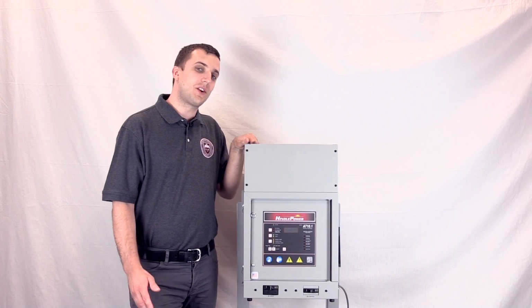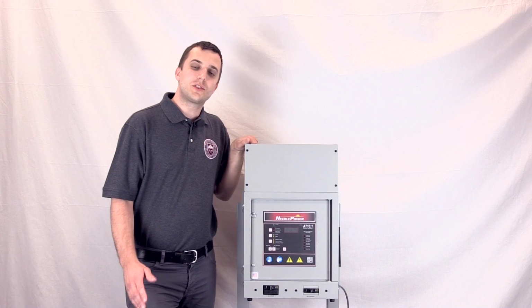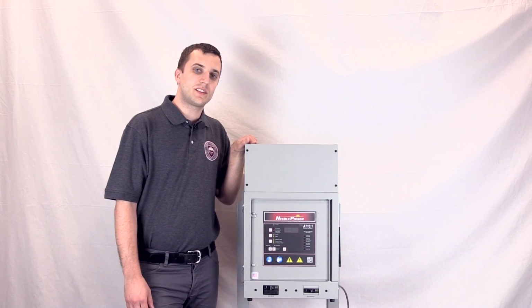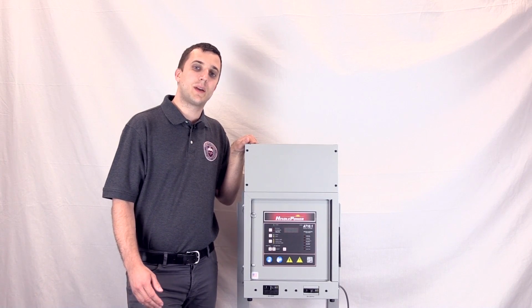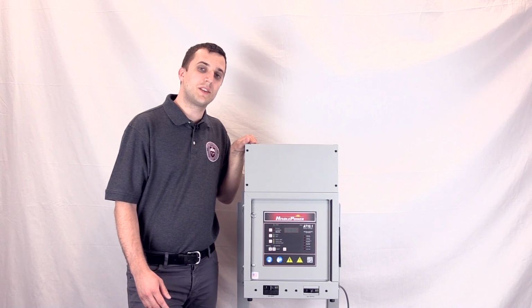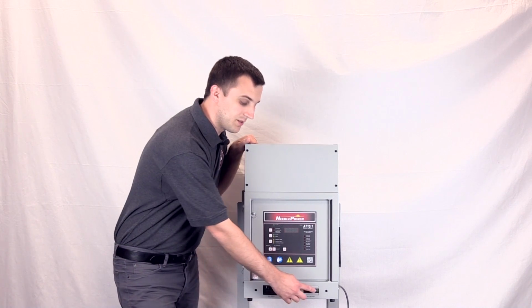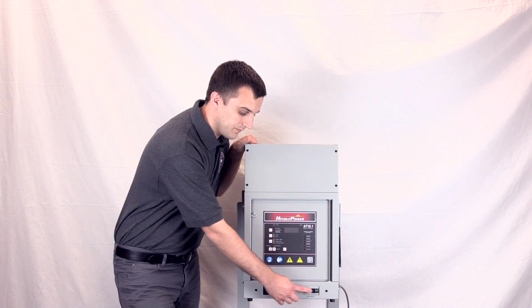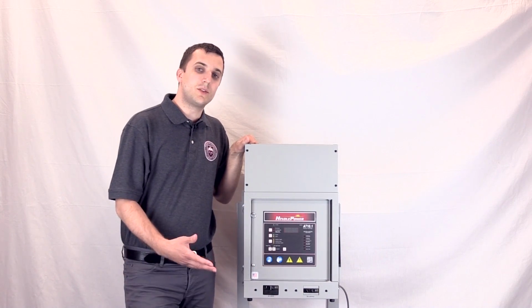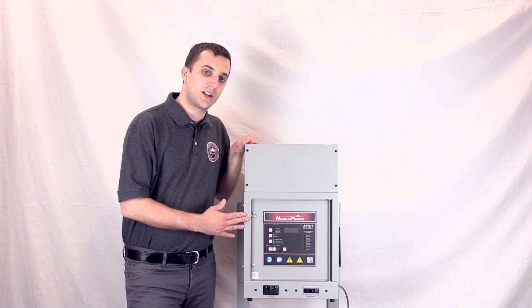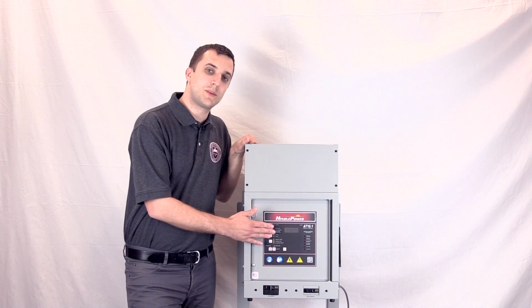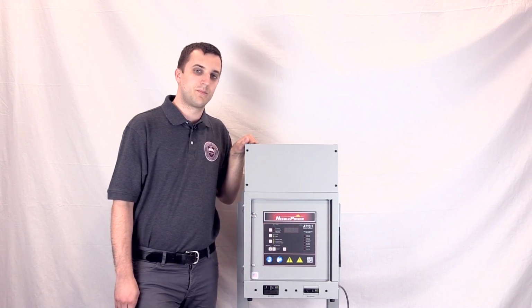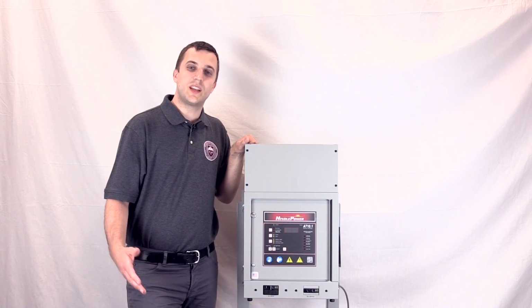Step 4, starting the charger. First, we want to turn on the DC disconnect that's between the battery and the battery charger. Next, we want to proceed and turn on the DC circuit breaker that's on the battery charger. Once we do this in a real situation with a battery connected, the battery voltage will come up and display on the battery charger. Next, we want to go to the AC side.